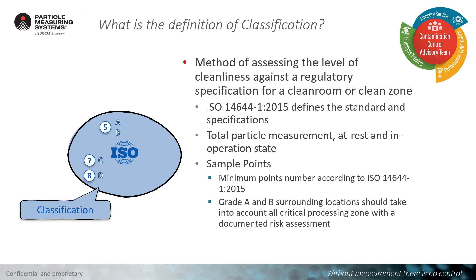Regarding the association between the pharmaceutical grades and the ISO classes: grades A and B must comply with the ISO 5 requirement in an at-rest occupancy state, grade C the ISO 7, and grade D the ISO 8. To declare that a clean room or a clean zone created by equipment is classified, we must measure the total particle count in two different occupancy states: at rest and in operation.